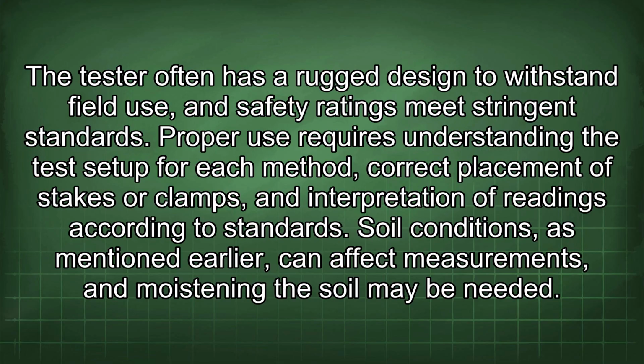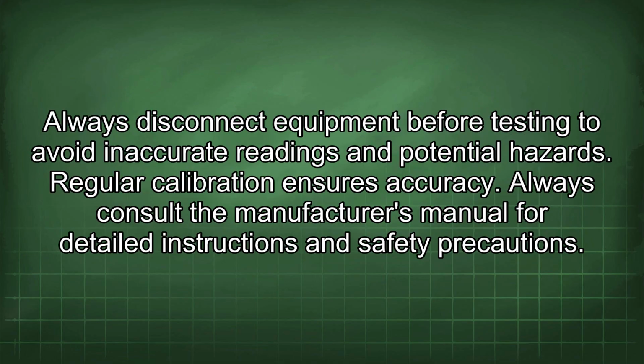Proper use requires understanding the test setup for each method, correct placement of stakes or clamps, and interpretation of readings according to standards. Soil conditions, as mentioned earlier, can affect measurements, and moistening the soil may be needed. Always disconnect equipment before testing to avoid inaccurate readings and potential hazards. Regular calibration ensures accuracy. Always consult the manufacturer's manual for detailed instructions and safety precautions.